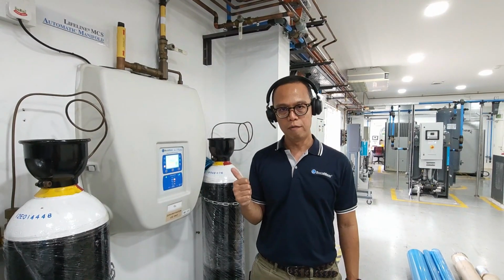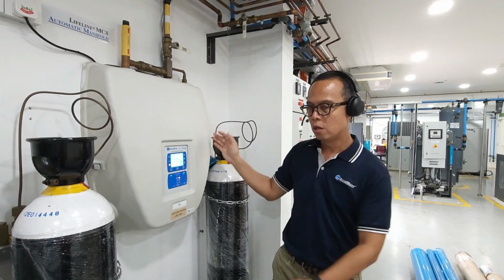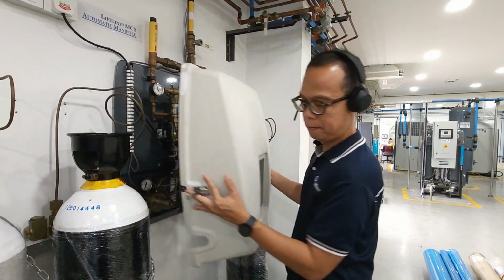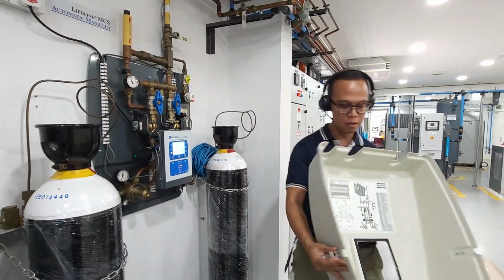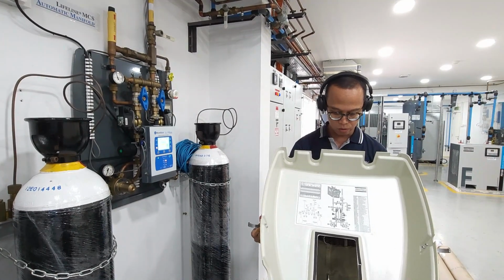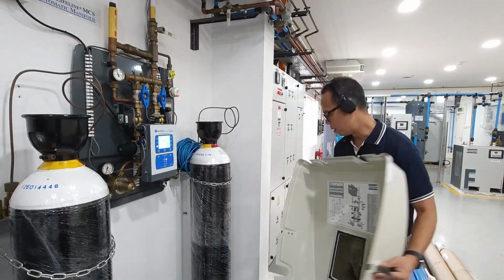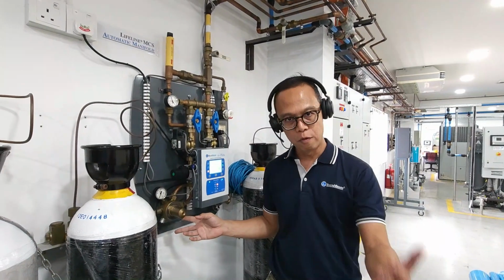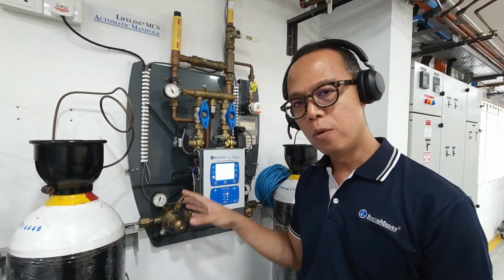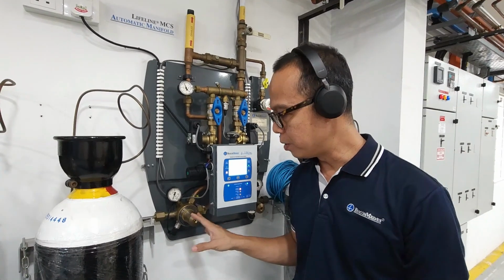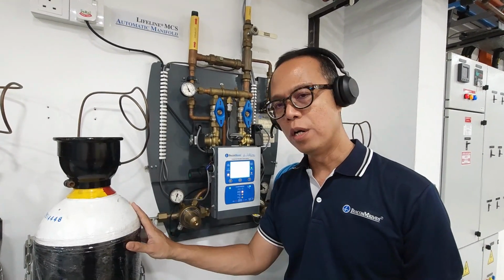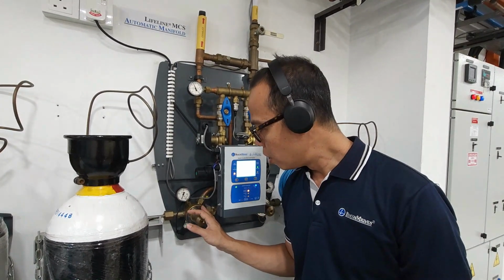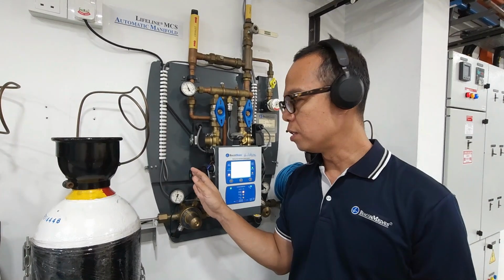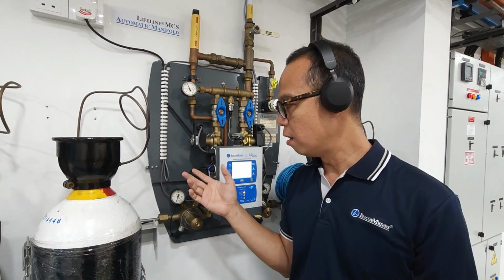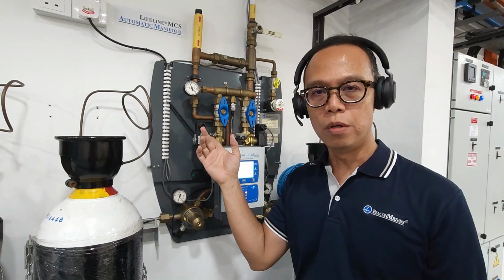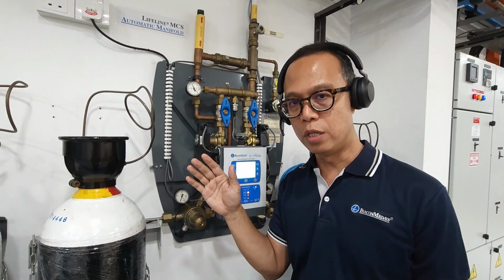Okay, going over to the Lifeline automatic manifold. This is no stranger to you. I'll show you the insides. It's a very simple unlocking mechanism here and here. And on the inside panel, there's a quick guide on wiring diagrams and the components of the equipment. Going in, this manifold is special to BeaconMedaes because we use two-stage regulation. The first stage regulator takes up to 150 bar down to 15 bar of pressure. Going up to the second stage regulator, delivery pressure depends on what kind of gas you are delivering, either 4 bar, 7 bar, or 11 bar. A solenoid valve to open and close. This solenoid valve, if there's no electrical power, will open.